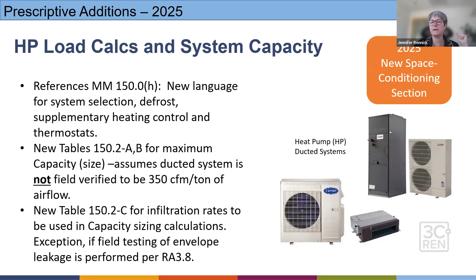I'm going to clarify here, but this is a new section specifically for looking at your heat pump load calcs and that system capacity. And there's also a prescriptive table for infiltration rates you're supposed to use when sizing your equipment. The exception to that is if you actually do field testing of envelope leakage. That means having a HERS rater, or now it's going to be called an ECC rater, come out and do a blower door test. And this again becomes the baseline. You can do a performance method and go that route as well.